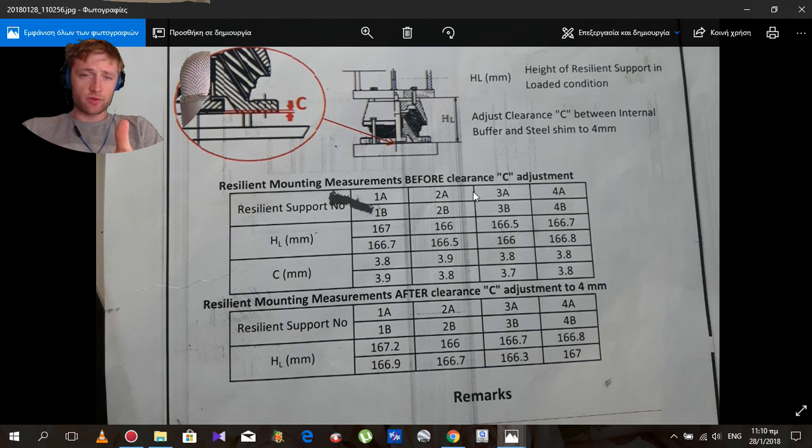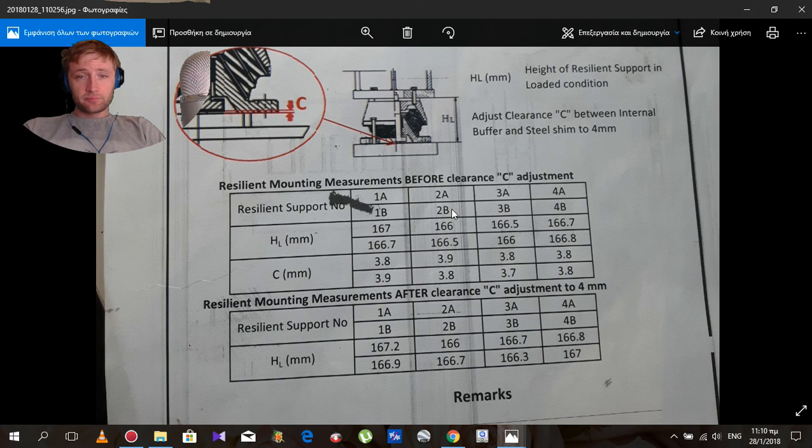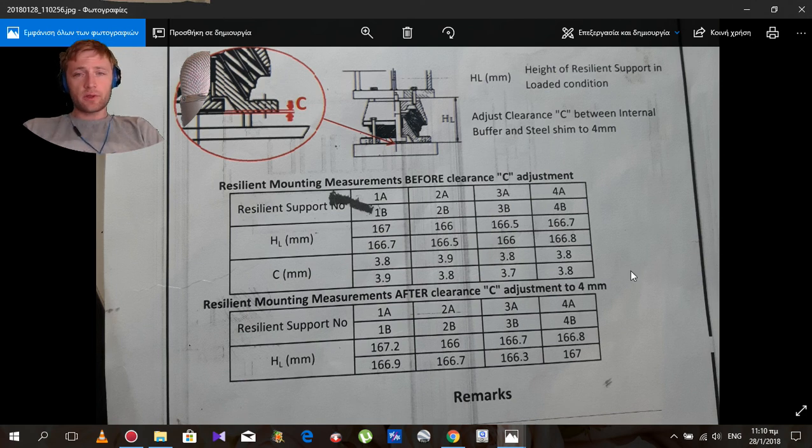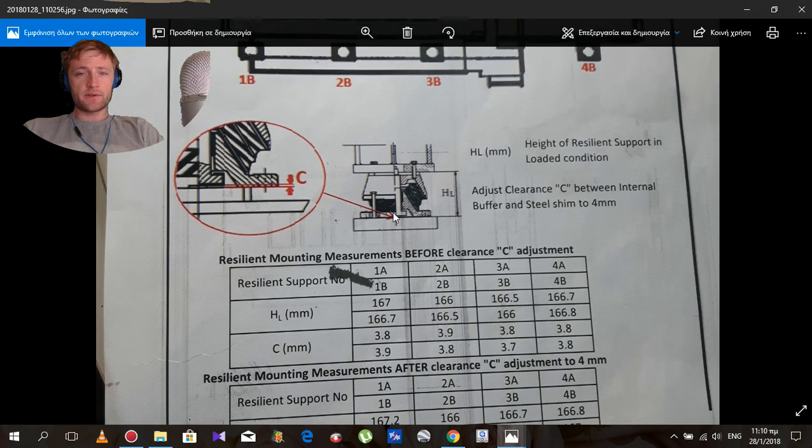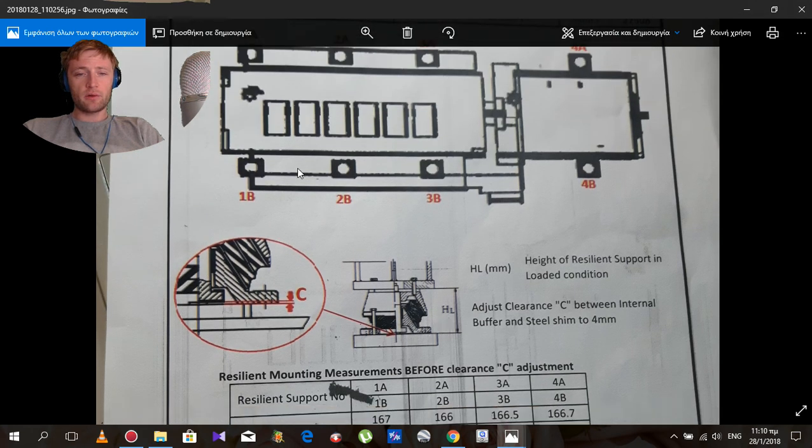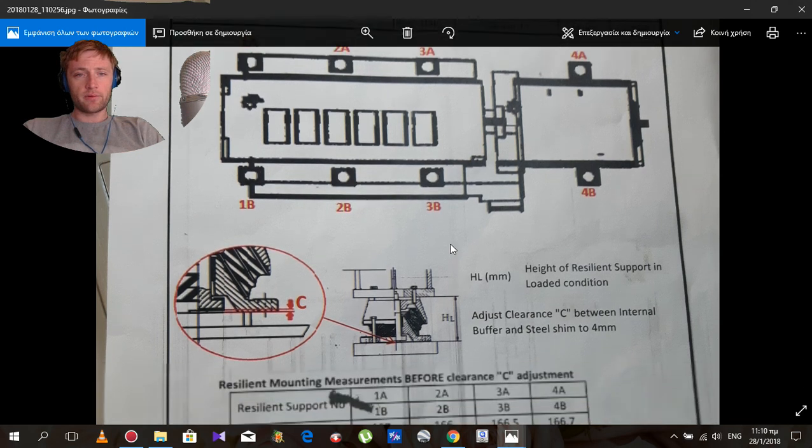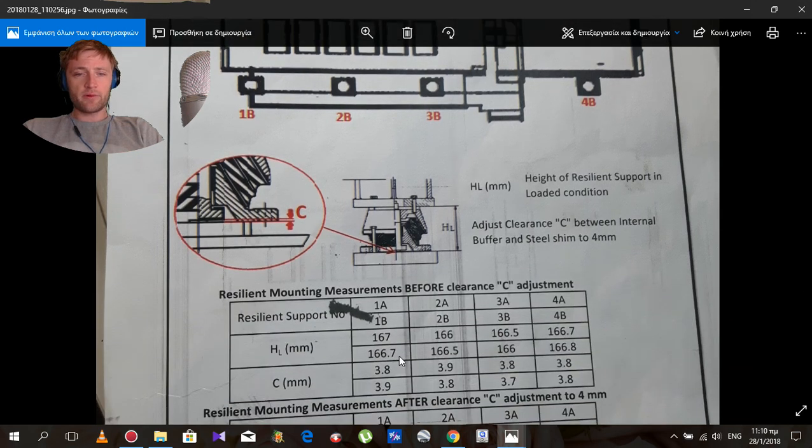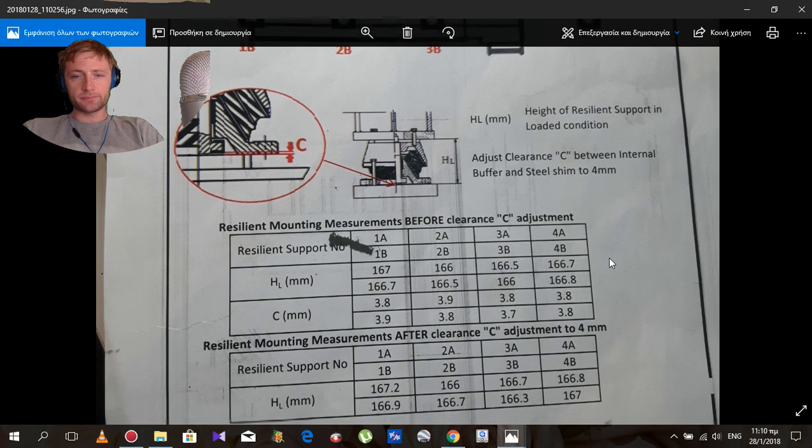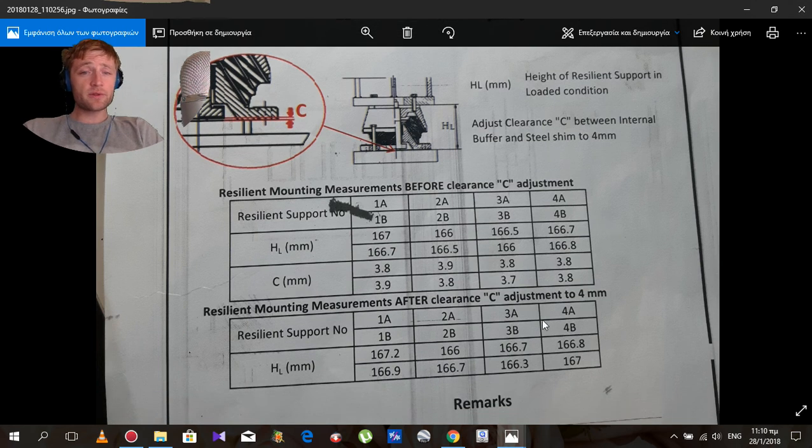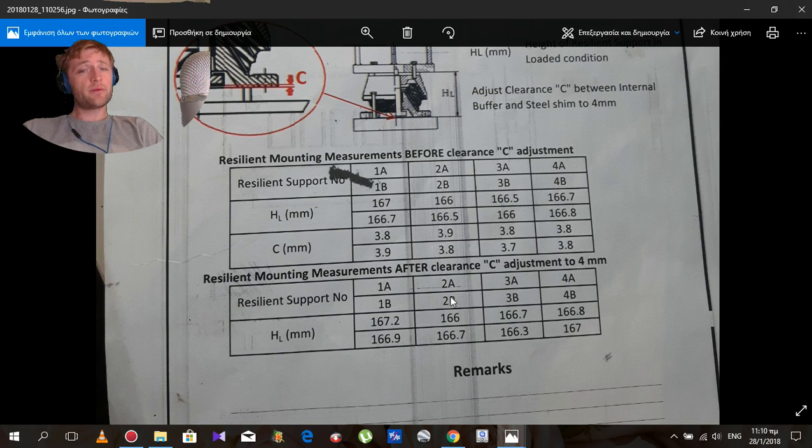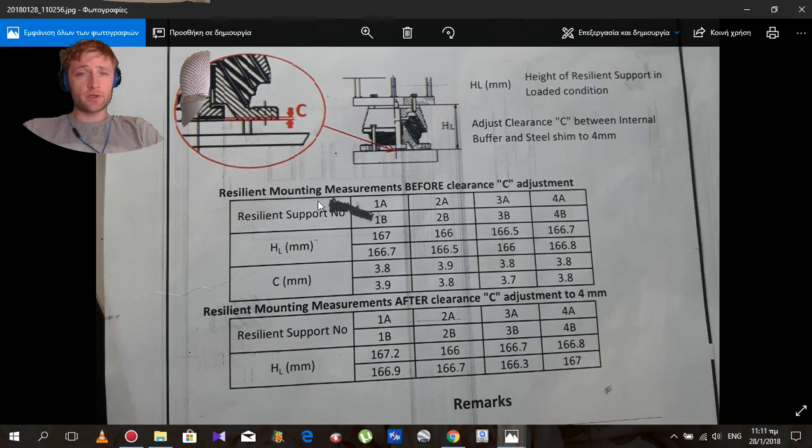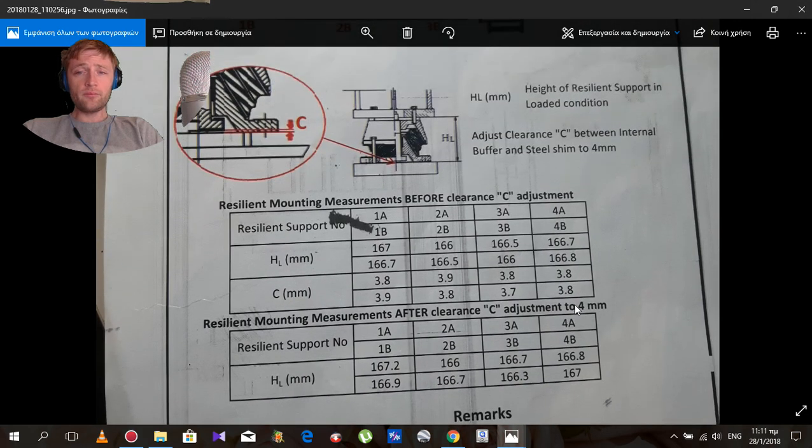We have before the measurement, before the adjustment, what were the measurements of each side. As you can see, 1A is 167 HL here, it refers here. 1B refers to the other side: HL and C, the inner side of the resilient. And after the adjustment, when we adjust the C to 4 millimeters, how the height will change, this HL height. That's it.